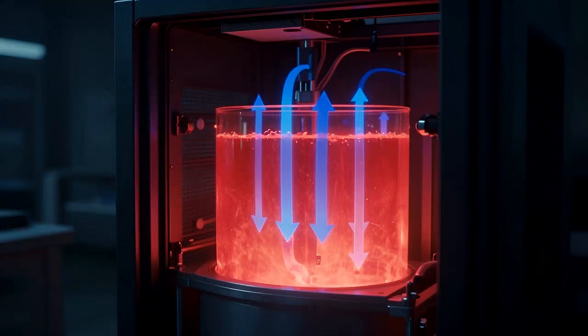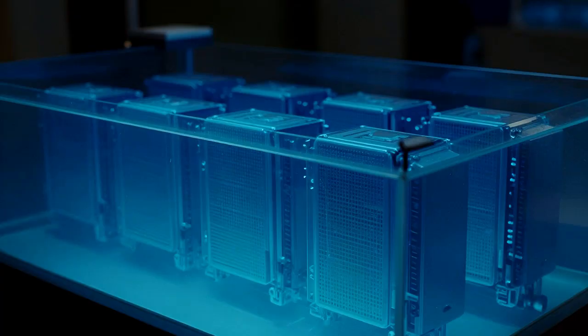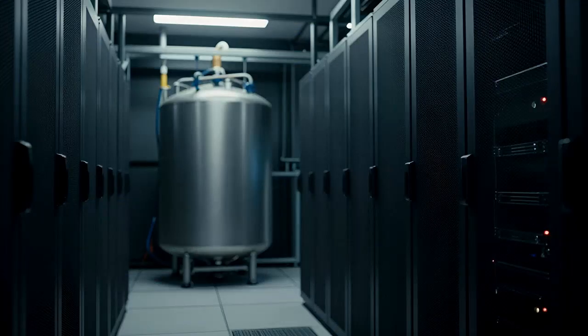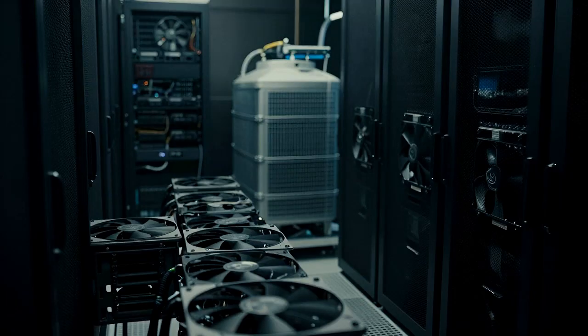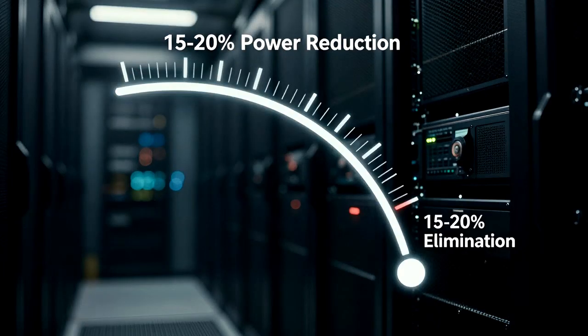Immersion cooling achieves an unprecedented 100% heat capture. There are no thermal gaps, no localized hotspots, and absolutely zero need for supplemental air conditioning or internal server fans. The complete elimination of server fans alone is a massive victory, instantly reducing a server's total power consumption by 15% to 20%. The immersion cooling landscape is fiercely divided into two distinct technological pathways, each with its own benefits and deep complexities: single-phase and two-phase.